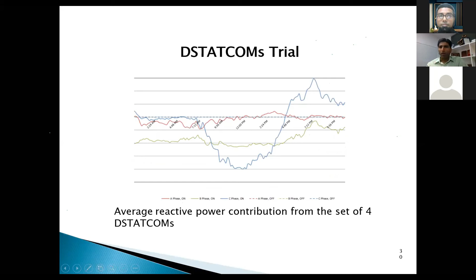We did a sensitivity analysis and have papers helping local utilities determine optimal STATCOM placement. You can see it's an unbalanced injection—when off, there's no reactive power injection, but when on, the reactive power absorption and injection across phases significantly reduces the unbalance, putting voltages of all phases into the right band.